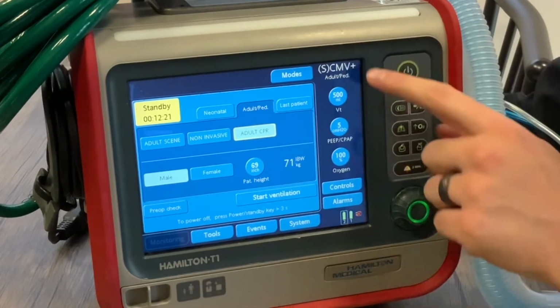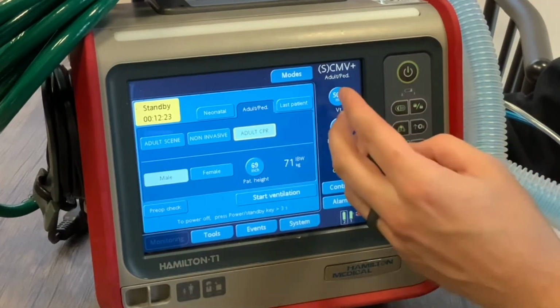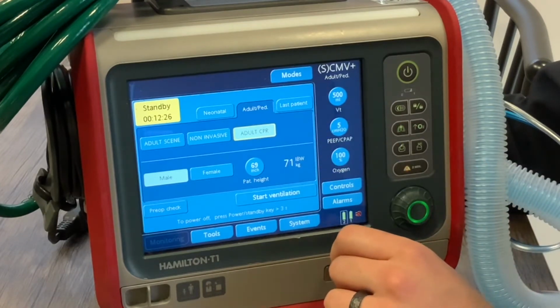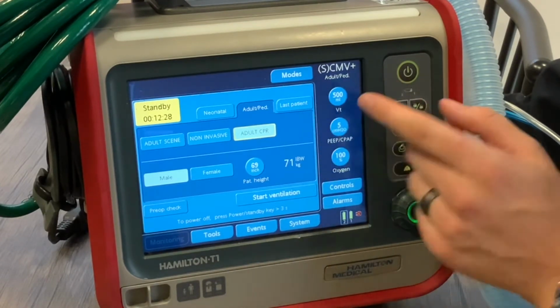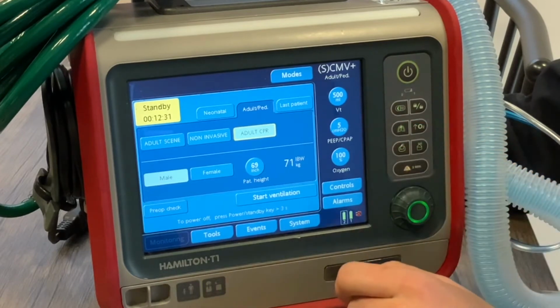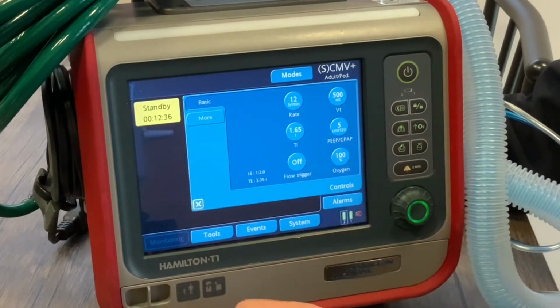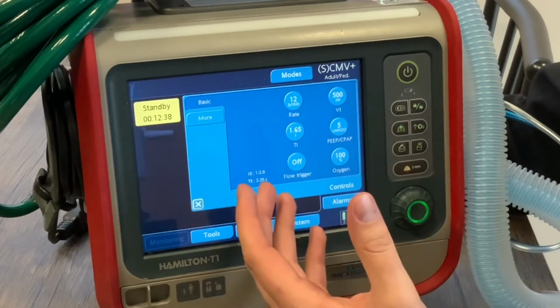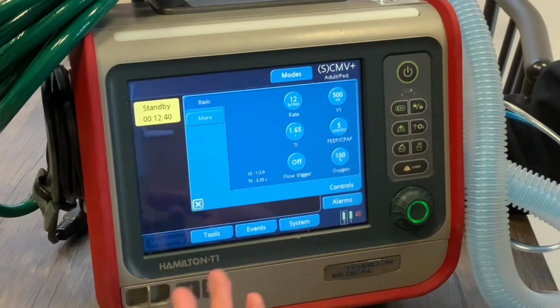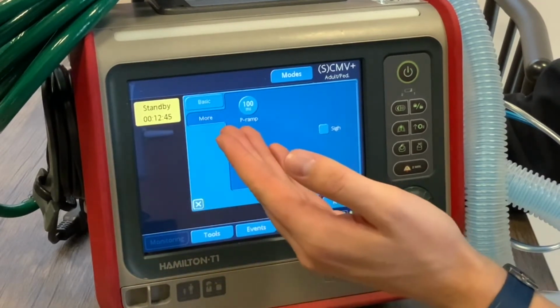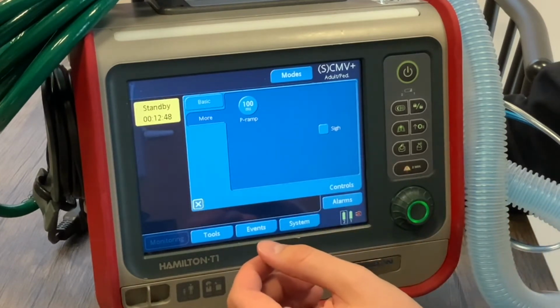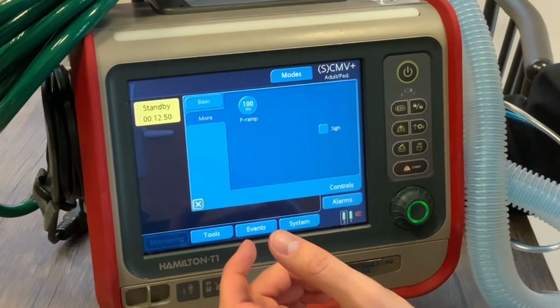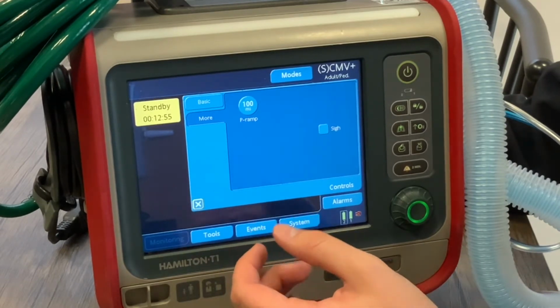Coming to the right, again, we have the mode that's currently selected and the 3 most common variables used to change using that mode for CMV plus: tidal volume, PEEP, and FiO2. Below that, it brings us to the control screen. This is where you make adjustments to things like respiratory rate, PEEP, or tidal volume. If we go under more, it brings us to P-ramp and some other variables like ETS, depending on what mode you're in. Again, see the other video on modes for more in-depth information.